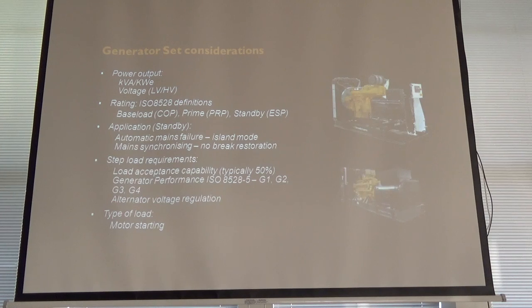So, emergency standby power, by the definitions of ISO, it has a capped limit per year of 200 hours of running, an average variable load of 70% of its rating. So, basically 70% of 1100 is its maximum average variable load, but there's a cap of 200 hours per year. The reason why you select a unit with that limit, it affects the engine driver itself. If you want it running for a longer period, you might end up with a larger engine basically for a given output. So standby rated, prime rated power, again average variable load of 70% of its rating, but PRP definition means it can run for an unlimited period of time or period of hours per year. Okay, so there's no cap on the running for that, which is key.